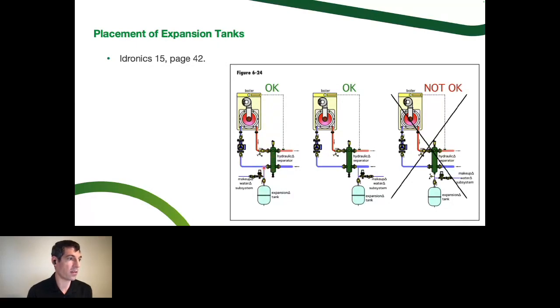The expansion tank is on the coldest water on the return to the boiler. So that's good just for the longevity of the expansion tank. The rubber diaphragm, or bladder, whatever style that you're using, if that's on the hot side, even if it's on the inlet to the system circulator, the warmer temperature is something that can reduce the service life of that component. Maybe not drastically, but best case scenario, I'd put it on the coldest spot right before the boiler circulator.